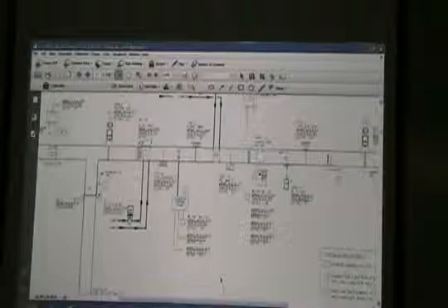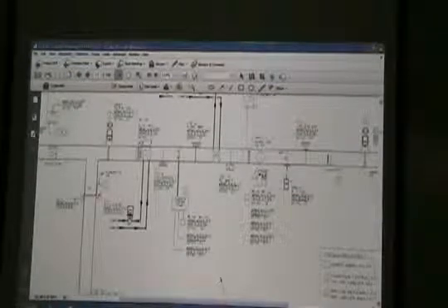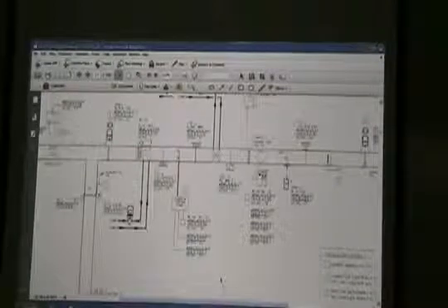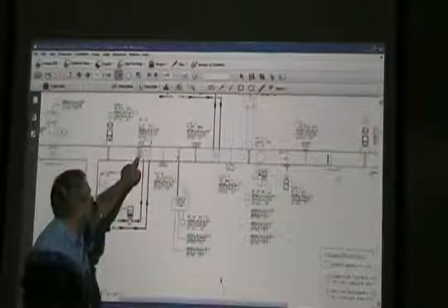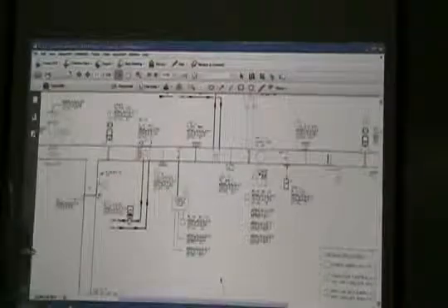So this is the bypass right here, inside that air handling unit. So it's not drawn truly correct right here, because this should actually be two sets of dampers, and this coil is a little smaller than the actual duct. So that's how you do it.